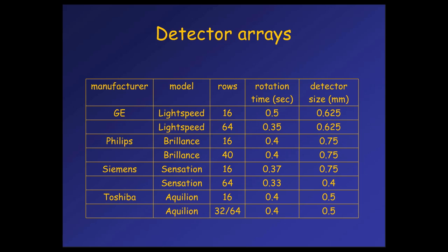Different vendors have different configurations of scanners. In modern scanners, you will have a number of rows that vary between 16 and 64. In the future, there's going to be more than 64. Rotation time of the gantry varies right now between one-third of a second and one-half of a second. The size of the detectors on the detector array vary from 0.4 mm to 0.75 mm. So sub-millimeter resolution in all scanners.